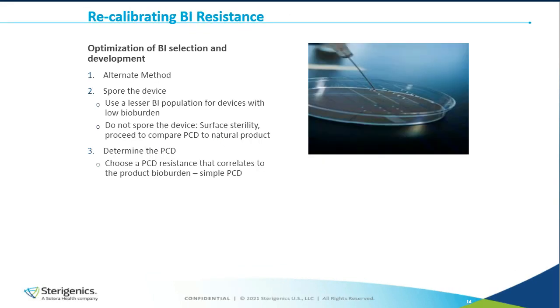I will now cover one important element. We are using biological indicators to do the validation, and typically we place a 10 to the 6 BI in the worst case location in a product. But there are alternative methods that can be acceptable. We can still continue to spore the device, but instead of using a 10 to the 6 BI, we could use a reduced population BI that would be more in line with the true bioburden of the device. We could also do a test of sterility and a graded exposure cycle without sporing the device, using PCDs. We can also try to develop a surrogate PCD that has a resistance more correlated with the true bioburden of the product.